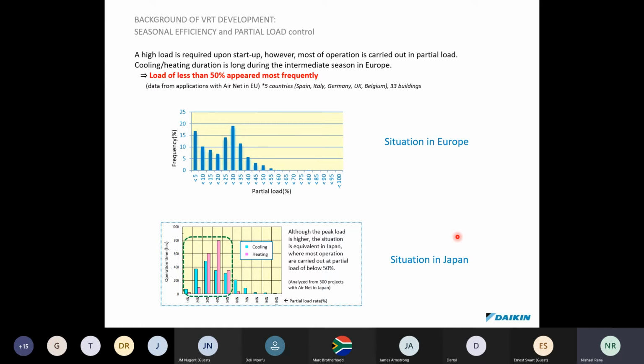That means a high load on startup, and during the day, when the office is being cooled and people are going for lunch, or moving from one open plan office to the canteen or the boardroom, the point is that the loads vary. What the VRT does is increase the refrigerant temperature automatically. How does increasing the refrigerant temperature help? Number one, you don't end up overcooling the space. Number two, you use less work to make 11-degree refrigerant as opposed to 6-degree refrigerant temperature.